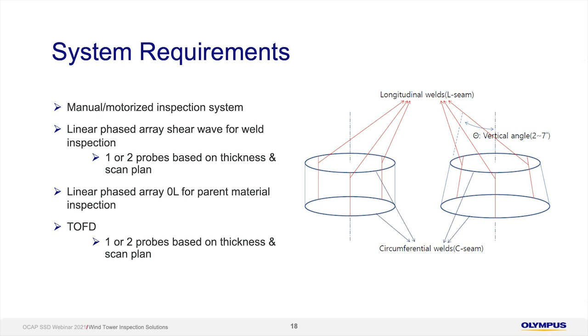So one solution, of course, is to use the OmniScan. And over here, it can be connected to the WeldSight software to control the instrument. And you can have different scanners from manual to semi-automated. So here is one of our offerings, which is a fully automated inspection crawler. This fully mobile solution is actually run using the Focus PX and WeldSight software.